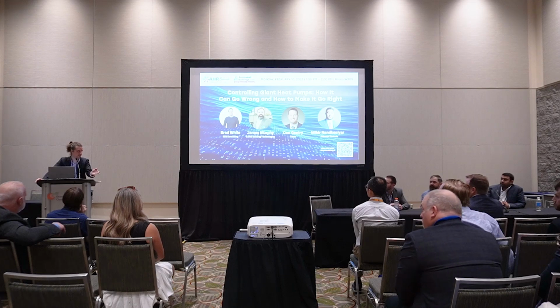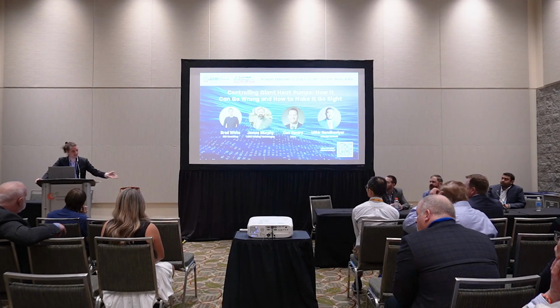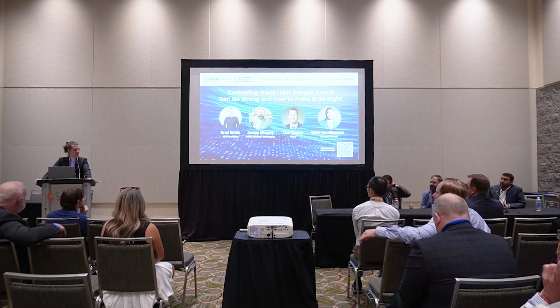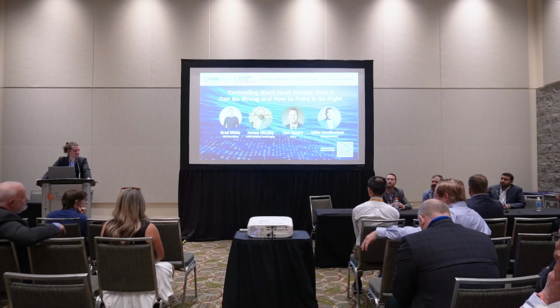Volume is, again, a big issue though. We've got a school we worked in. They put in a wastewater heat recovery, but it turned out there wasn't enough waste, and they couldn't use it. So they spent, God knows how much public money, on this heat pump that they can't use because somebody didn't get the system volume right. So volume is huge with heat pumps.